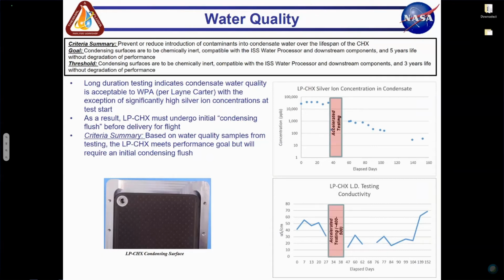And we worked pretty closely with Lane Carter at Marshall to look at our water quality. And we looked through pages and pages of water quality data from this. And basically everything looks acceptable to the WPA for the environment that we were testing in, except we have a gigantic, just a massive concentration of silver ions when we first start testing the laser process heat exchanger.